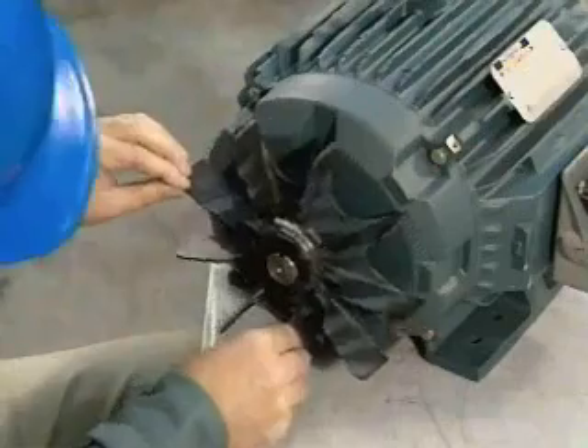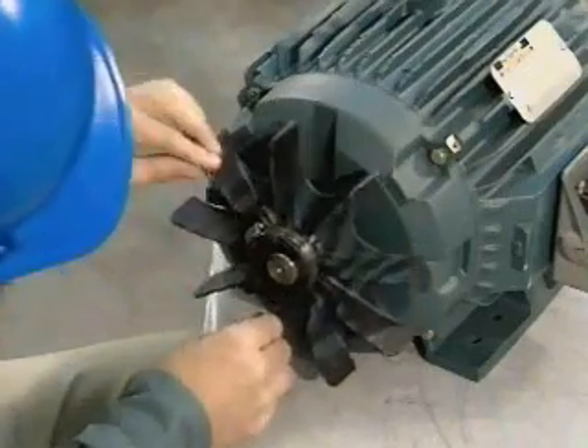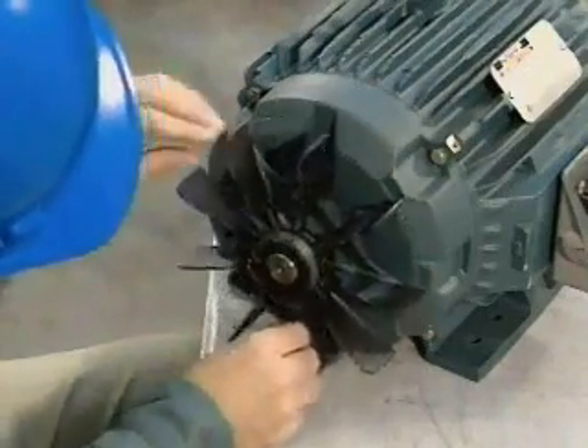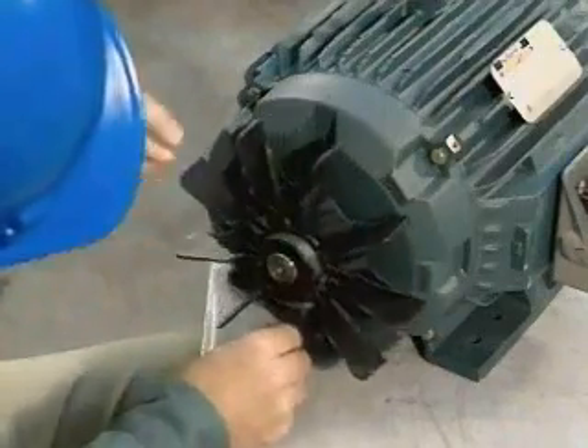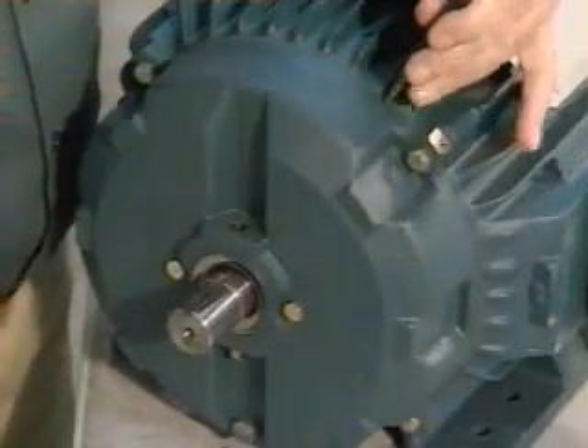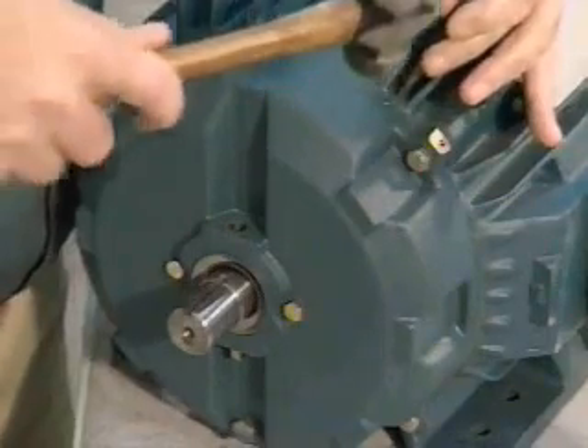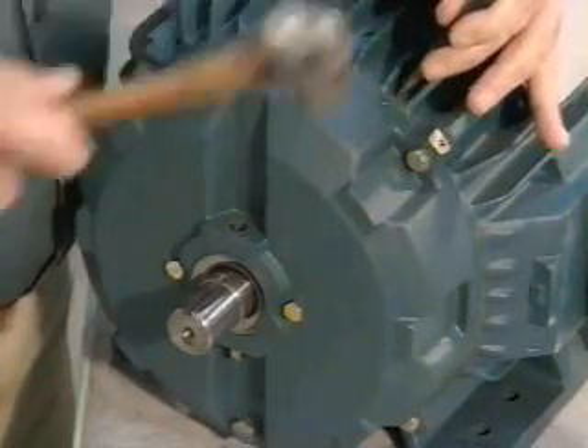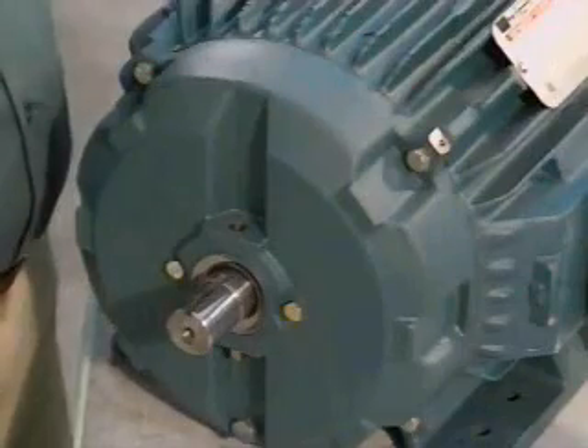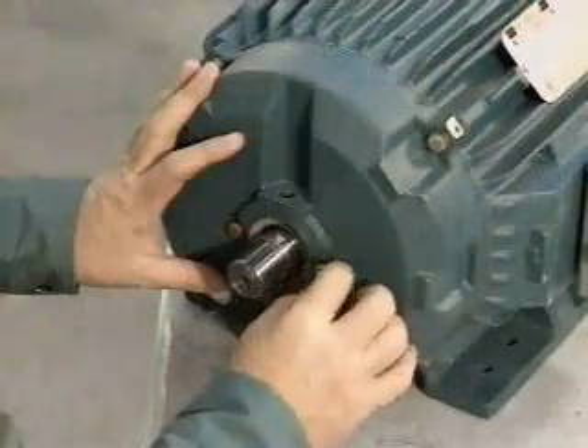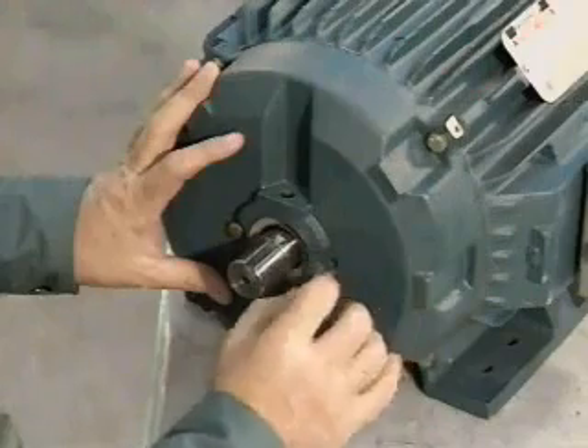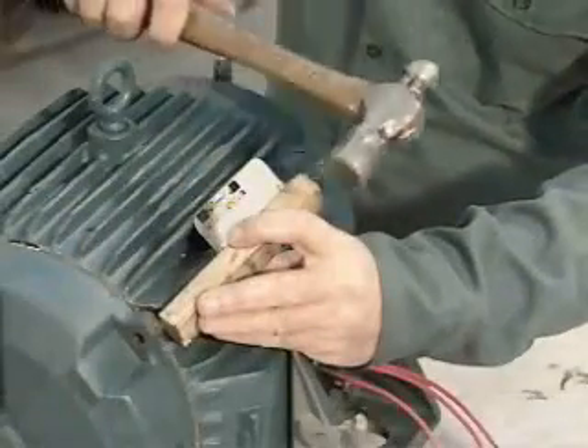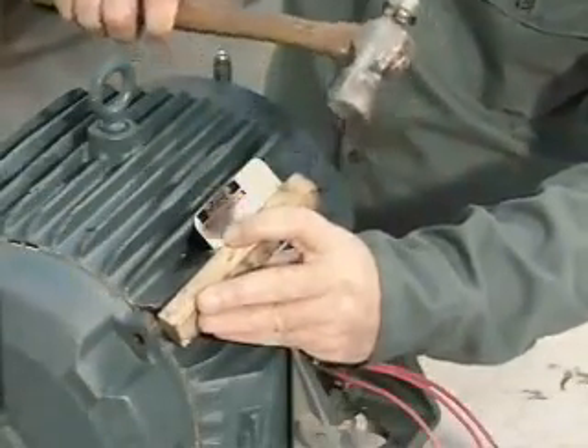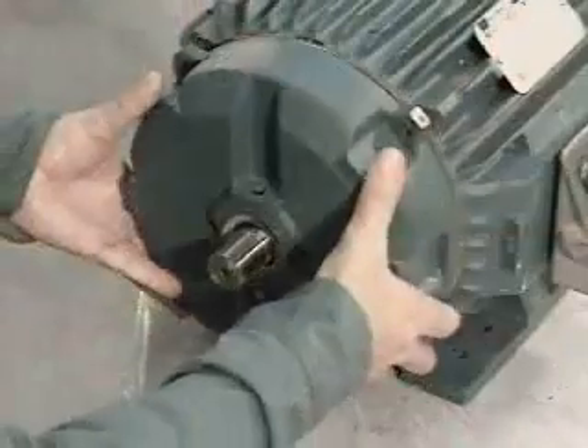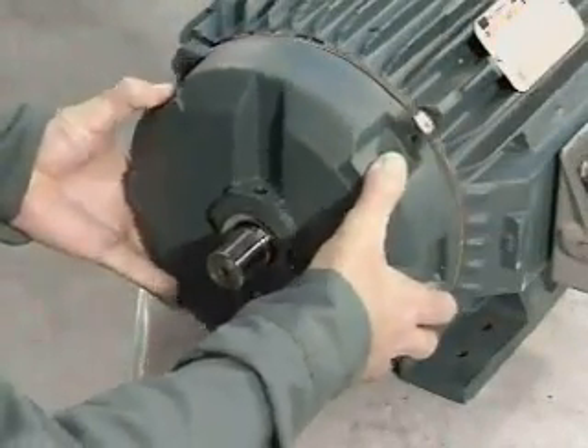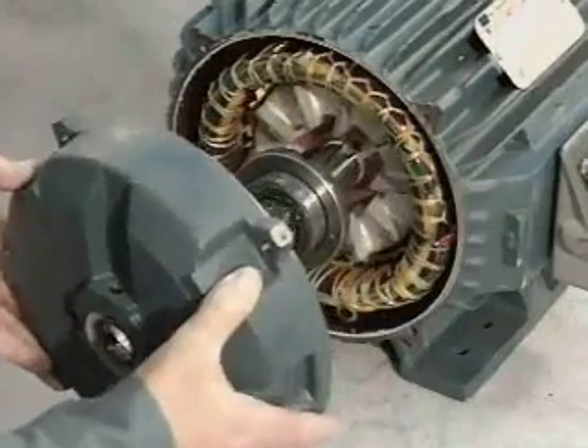Motors are disassembled by starting from the ends and working toward the center. When disassembling a motor, use techniques that will protect both the motor and yourself, and that will make the reassembly job easier. Begin disassembly of the motor by match-marking the end bells and stator housing to provide reference marks for proper end bell replacement later. Remove, bag, label, and store the bolts. Remove one end bell. Use a piece of wood or rubber mallet to help set it free. As you remove the end bell, take care so the rotor does not drop and damage the stator.